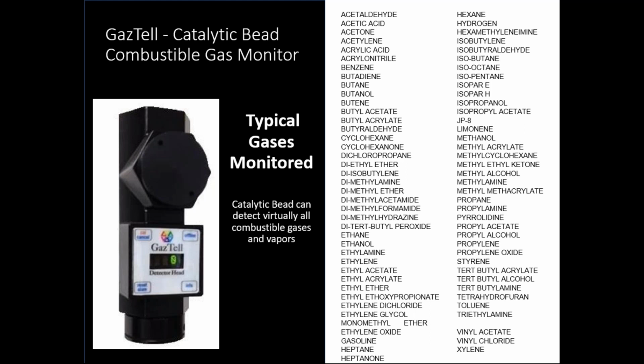Methane is considered the main gas. Methane is typically the gas most people use to calibrate, and this is for good reason. Methane has a high ignition temperature of 999 degrees. It also is readily available, and it's also very inexpensive. So when you use methane to calibrate your sensor, you're doing a couple of things. You're making an inexpensive calibration.